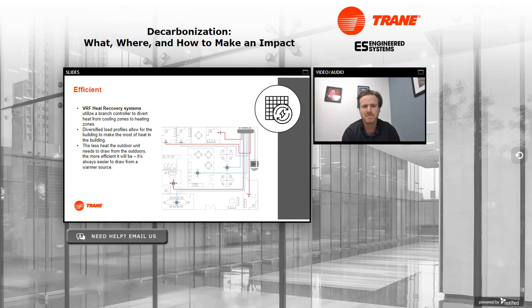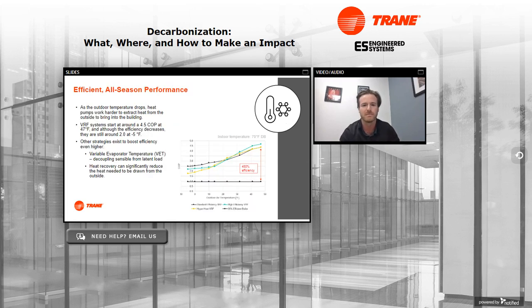So keeping in mind diversified load profiles really helps when designing VRF systems. If you can maximize where you may have cooling in one space and heating in the other space, because most VRF systems are air source, and what that means is you're going to be drawing cooling or heating from the outside, and as it gets cooler outside, there's less heat. So if you can source that heat from within the building, you're going to be really improving your efficiency on the whole system.